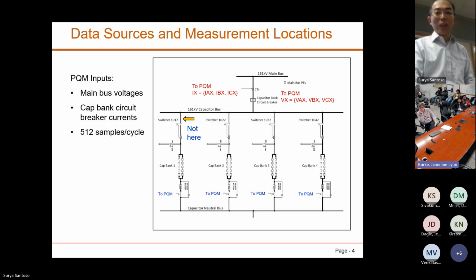The data comes from here - this is a typical layout of a transmission substation. You have a main bus, and coming down from the main bus you have a capacitor bus, which hosts 4 capacitor banks. This is a one-line diagram, meaning the A phase, B phase, and C phase all look the same.